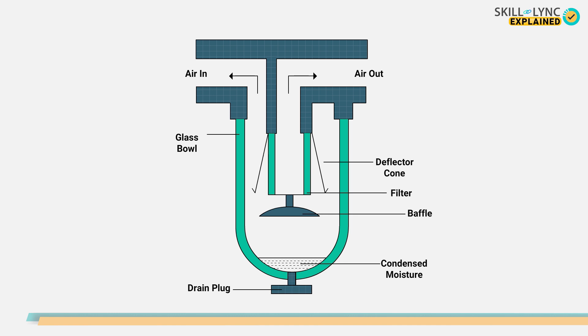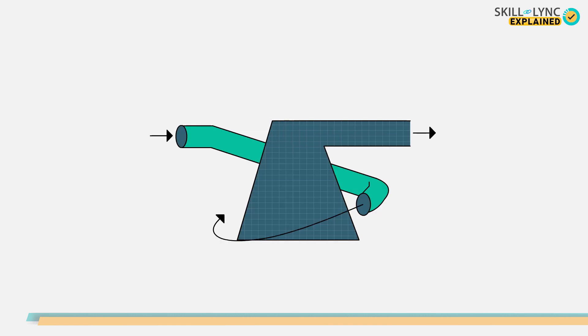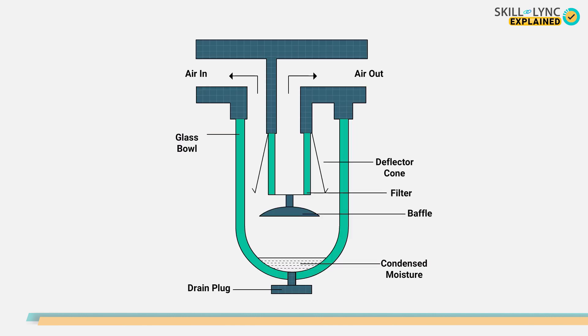The air at the inlet changes direction suddenly due to the shape of the dryer. Additionally, a deflector cone swirls the air, which causes the water in the air to be thrown outwards onto the walls of the separator and get collected in a trap at the bottom. The bottom has a drainage from where the condensed moisture can be easily drained out.